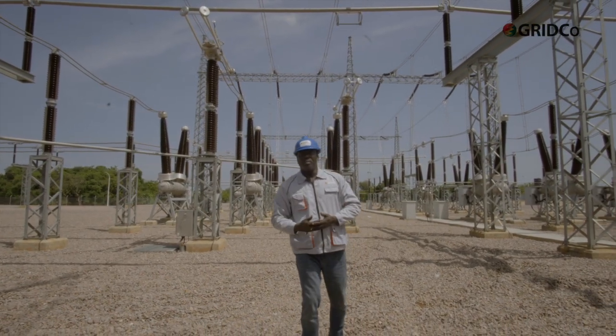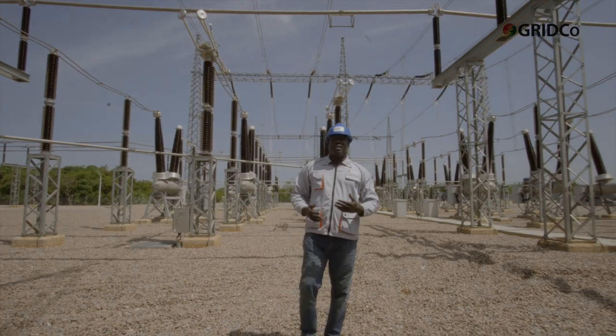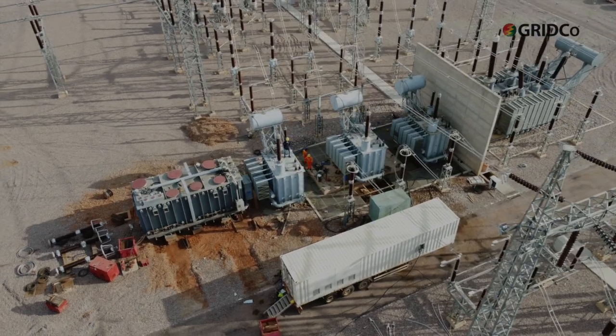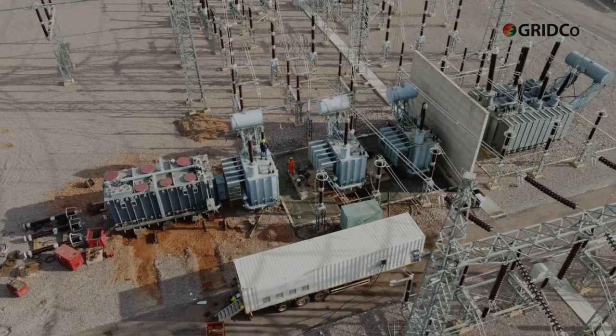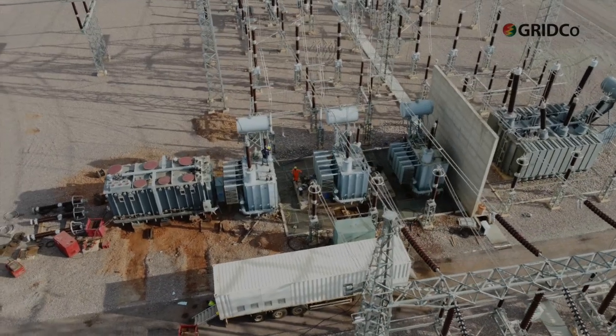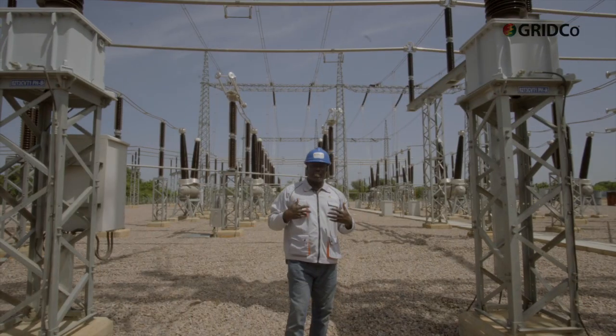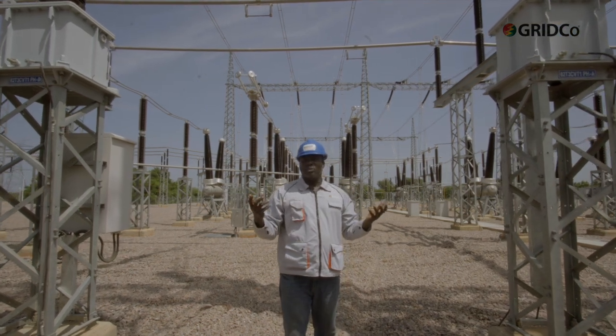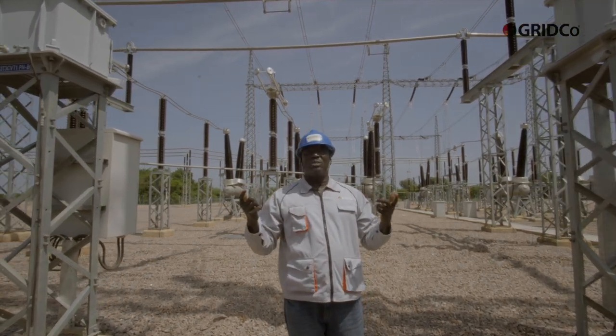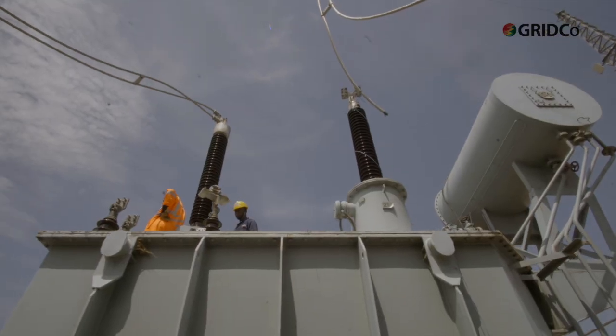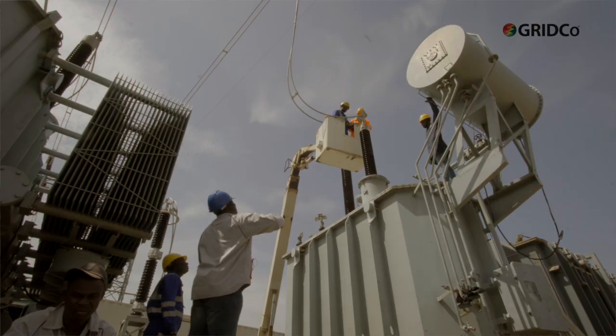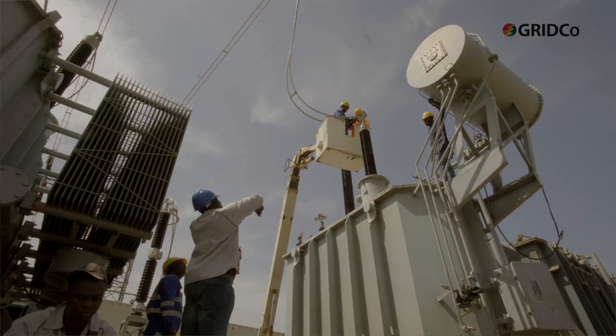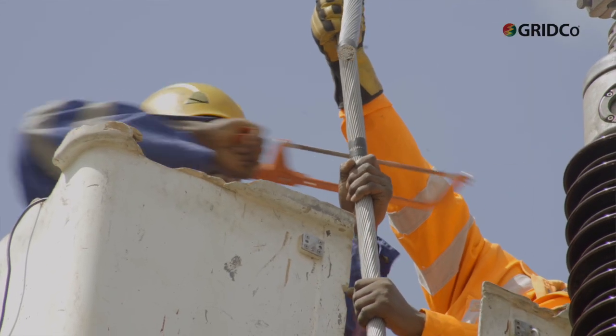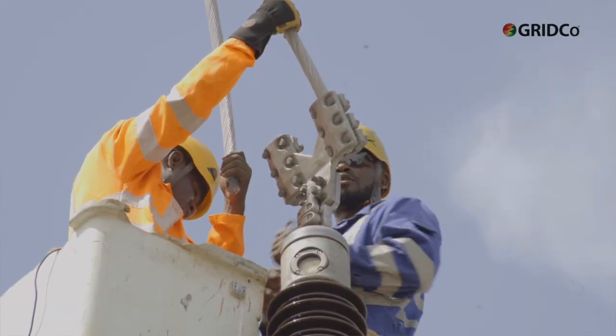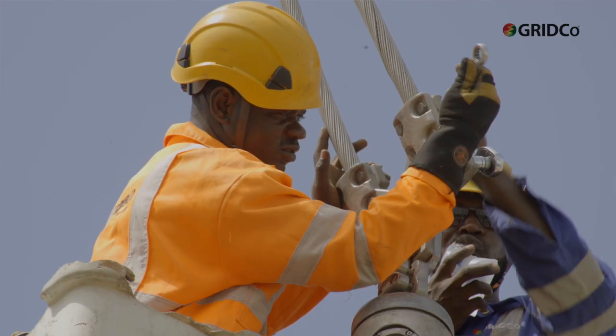So we needed to change the lightning arrestor that protects the input of the transformer. When there is a lightning stroke, it induces a higher voltage into the system, and we don't want our transformer to get damaged. So there is a need to protect the input of the transformer with the lightning arrestor. What the line people are trying to do now is to do the final termination of the transformer input, which is the 161. Then we will drop all the leads so that the PNC and electrical will do their tests.